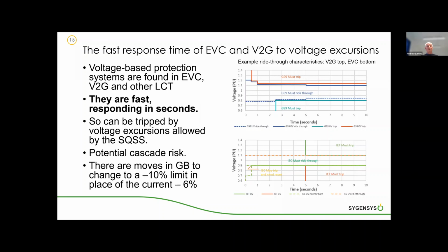And within the GB grid, there are also some thoughts of expanding the voltage regulatory range in terms of the lower limit, changing that from -6% to -10%. That's aimed at trying to give the DNOs greater flexibility in terms of dealing with the voltage drops that come from increasing loads. But the regulatory limits associated with tripping thresholds have very much been based around the current limits for voltage regulation. So there are some challenges there that we go into in much more detail within the Work Package 2 report.